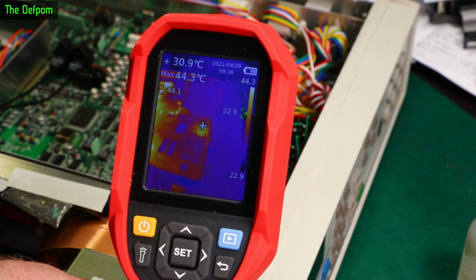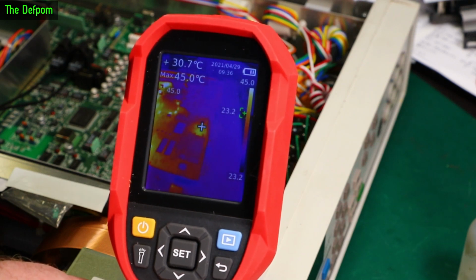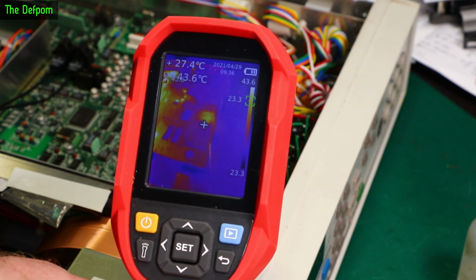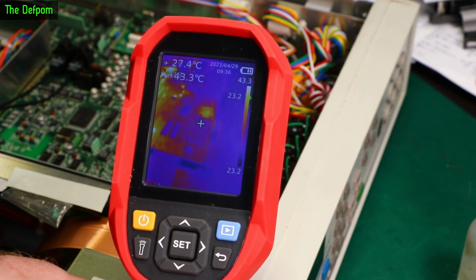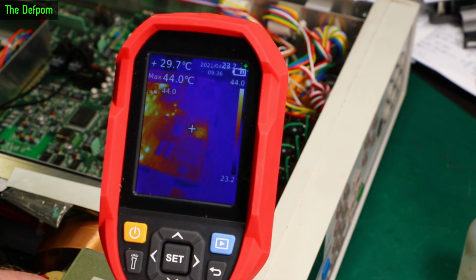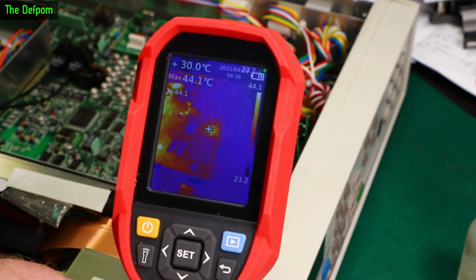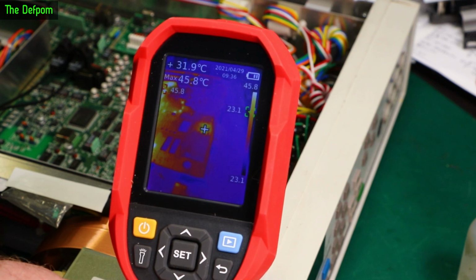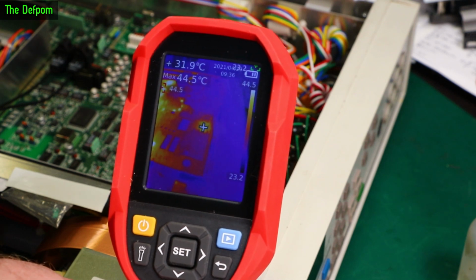And you see it's about 31 degrees. And the ones next to it are, well, you know, cooler than that. 27 or so, 26. Thereabouts. Alright, so that relay is getting warm, and that's known as being a problem. This is getting 32 there, so you can get 32.